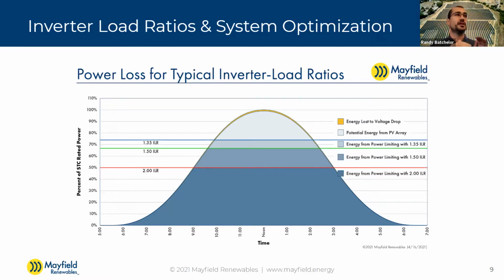Basically what happens is you can miss the inverter's MPPT operating window if the voltage is too high. The result is that instead of just clipping the power at the inverter output, the inverter can't actually put out any power during that period. That's because it's trying to find the maximum voltage to keep the current under the rated input current of the inverter, and in doing so it completely misses the operating window and sends output to zero. So anybody can look into hyperclipping, it's something to be aware of.